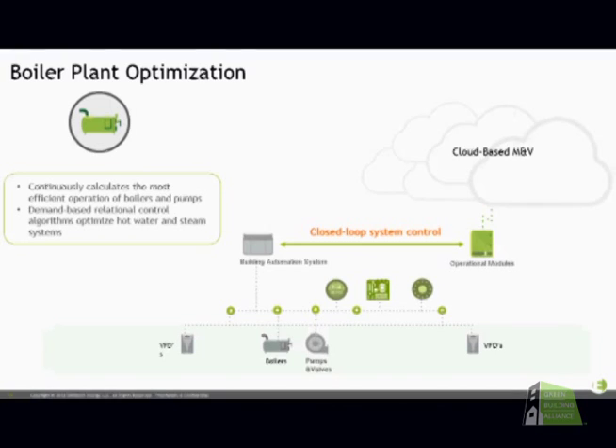If there's a lot of small buildings in a portfolio, I would start to look at making sure you have metering, make sure you know where everything's going, what the BTUs per square foot per year are for each of these little nodes, and make sure there aren't outliers. Start to clean up practices, thermostats, just collect data, form a baseline, and start to attack where the outliers are.